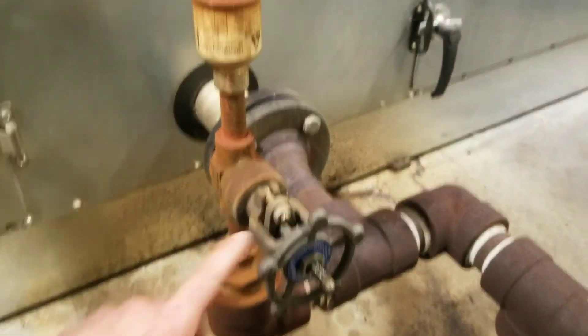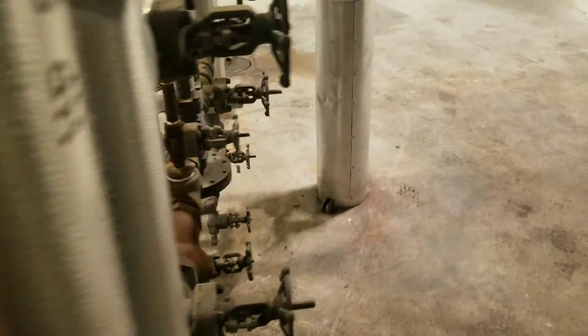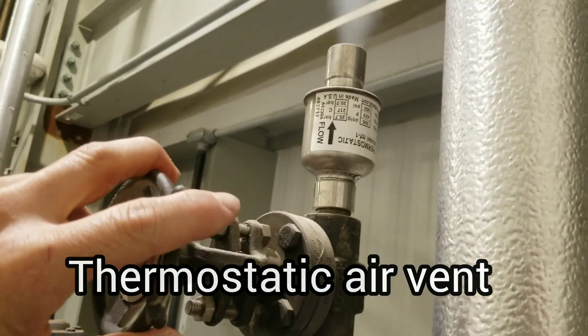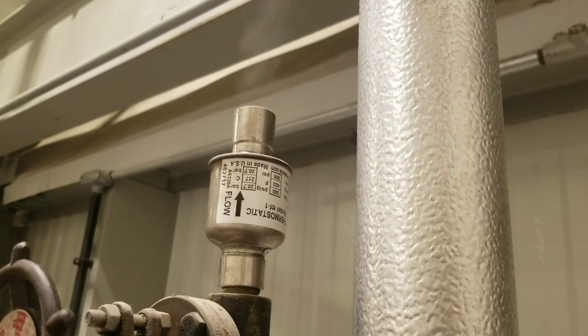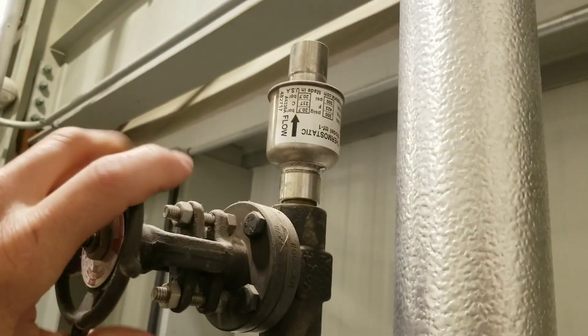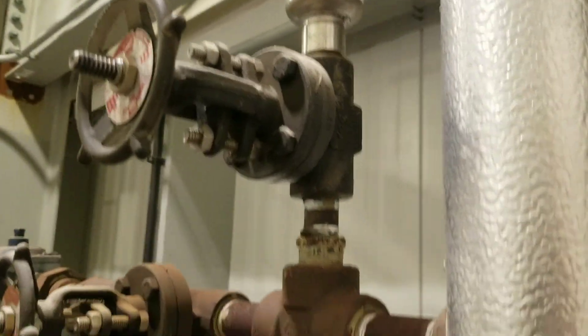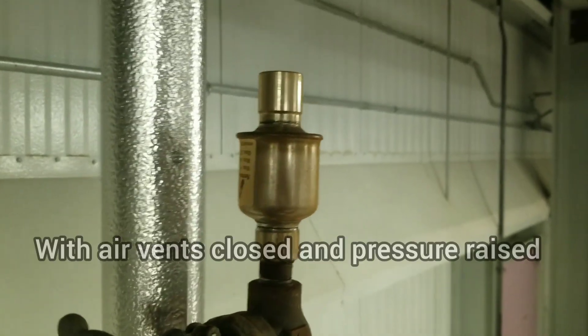Started at the top and I've got air vents closed now. We might have to replace some more of these, but for right now they're not leaking and we're looking good. Let's work our way down and go from there. These are our air vents we're dealing with. We're going to get them cracked open, and once that air vents out they stop. That's what they're there to do — the system's got to breathe. Literally every air vent in this building is closed.